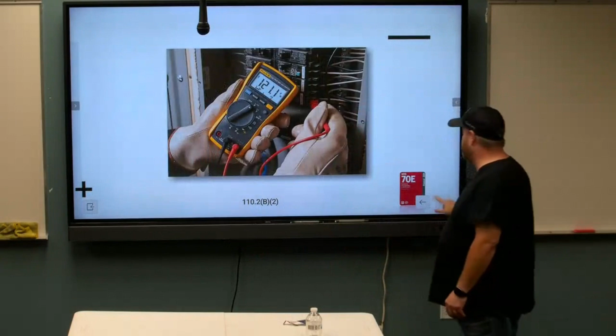We're exposed when we're taking meter measurements, when we're testing and troubleshooting, even when we rack large breakers in and out of equipment. Now, you can see here, you're not exposed to energized copper circuit parts or conductors, but he's interacting with the equipment in a manner that could cause an arc flash. You're racking a large breaker on and off of an energized bus bar. You gotta ask yourself, what could go wrong? A lot. It could fail, and it does.